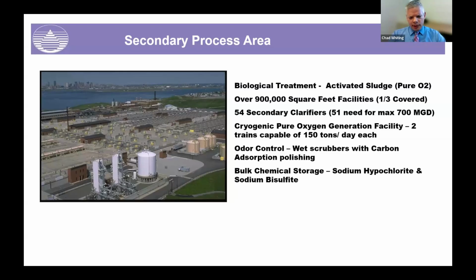We have odor control throughout the plant: all the covered tanks, the pump stations, and any of the buildings on Deer Island. The air is scrubbed through wet scrubbers, and then an additional pass through carbon for polishing. We use hydrogen peroxide for odor control also on our influent. As we see hydrogen sulfide levels increase in the summertime, we add peroxide to the influent to reduce those levels coming into the plant so they don't overwhelm our scrubbers.